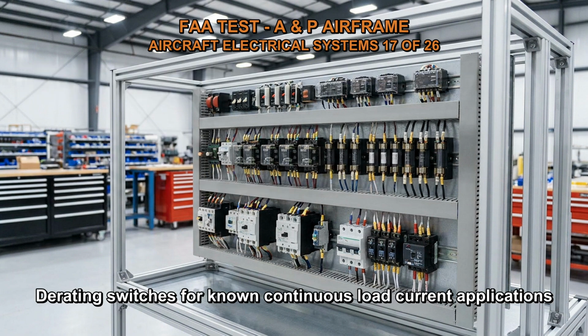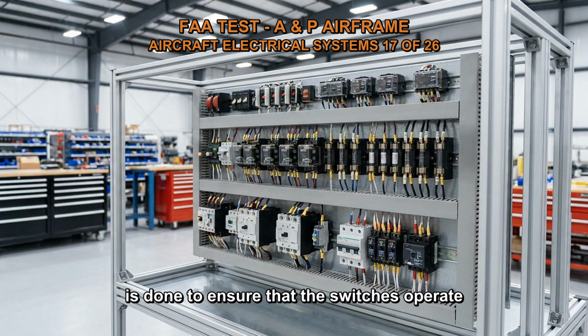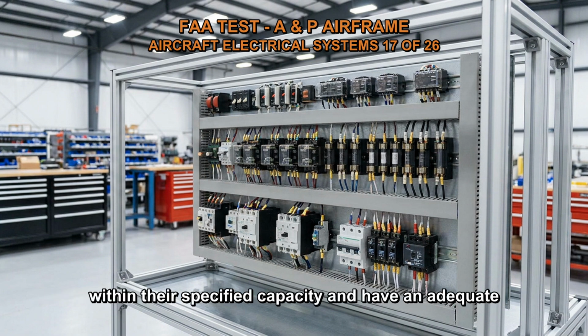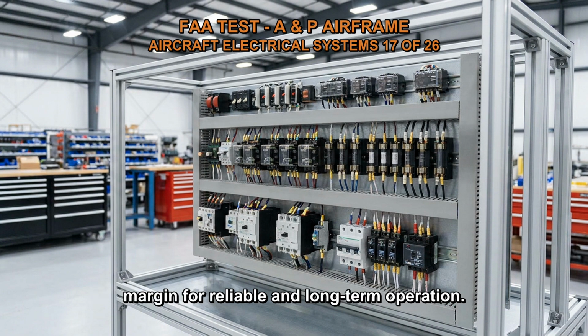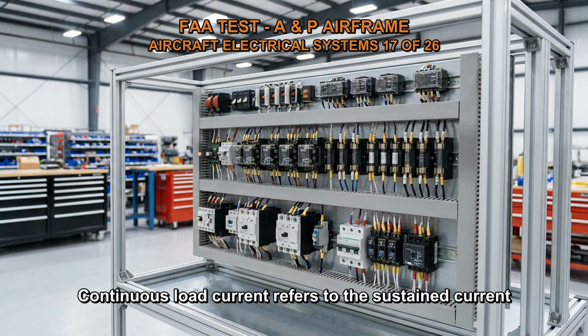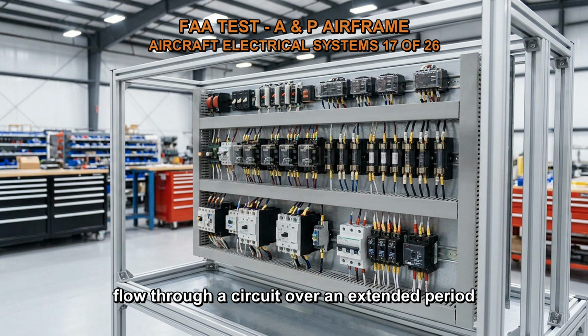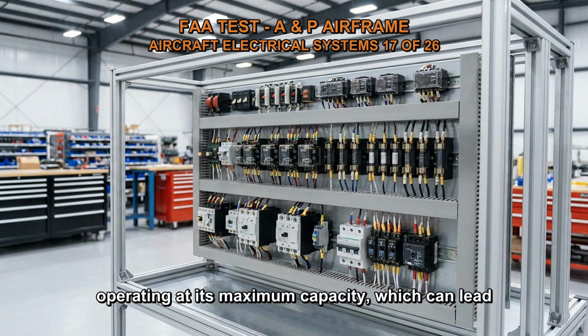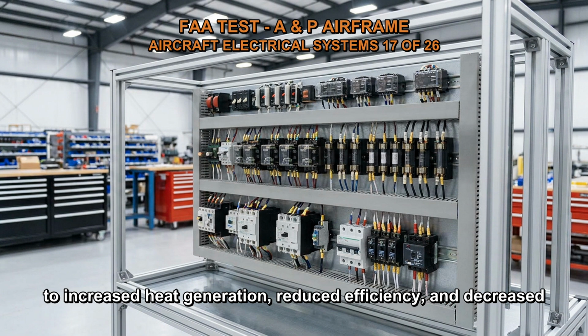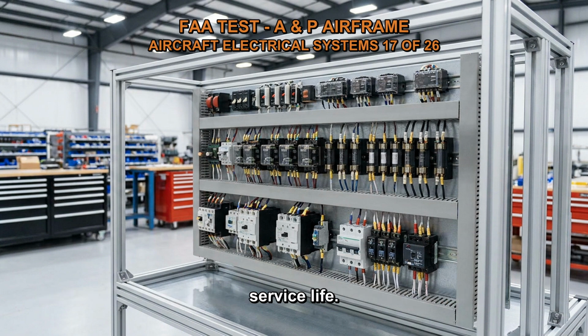Derating switches for known continuous load current applications is done to ensure that the switches operate within their specified capacity and have an adequate margin for reliable and long-term operation. Continuous load current refers to the sustained current flow through a circuit over an extended period of time. By derating switches, the actual load current is kept below the maximum rated current of the switch. This is done to prevent the switch from operating at its maximum capacity, which can lead to increased heat generation, reduced efficiency, and decreased service life.